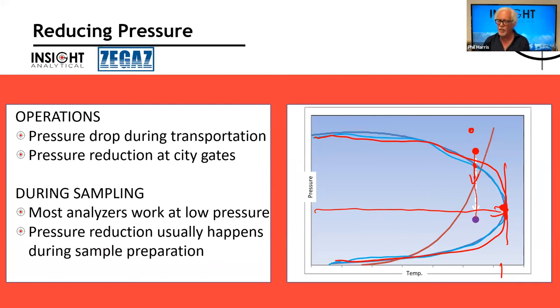Now, this can happen to us during sampling. Many analyzers work at low pressures. So if we lower the pressure, we may run through a dew point there. And so this often happens during our sampling side of things, our sample conditioning. Again, one of the things we're going to talk about with the ZEGAZ is it operates at high pressures, at line pressures, so that lets us get a true measure of dew point. It can also happen during transportation in the process, pressure drop along the pipeline. And once natural gas is coming into the city gates and starting to be distributed to homes, there's pressure drop that happens as well. And so these are common places for us to run into dew point issues.